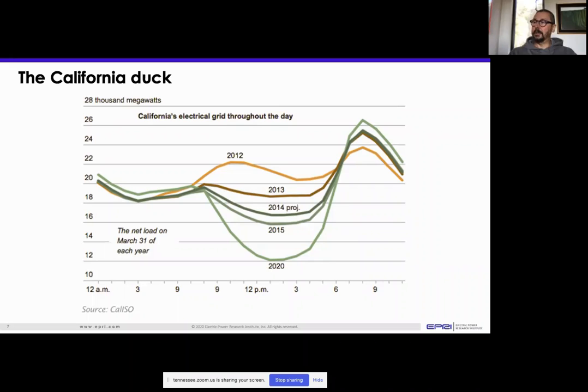As people put in more and more rooftop solar, the net load goes down when the sun is highest up in the sky, when solar generation is highest. The more people install solar on their rooftops, the bigger the belly of the duck becomes. So at some point in the middle of the day, the California power system has to turn down a bunch of generation resources. Their gas generation gets turned down, but sometimes you need to turn off things you don't necessarily want to turn off, because it's a problem for the system to turn on power stations that are designed to run at peak full time.